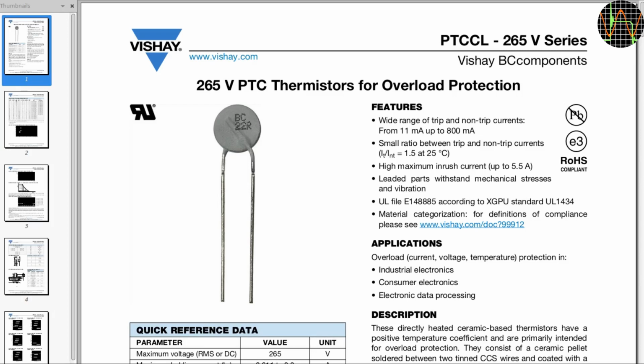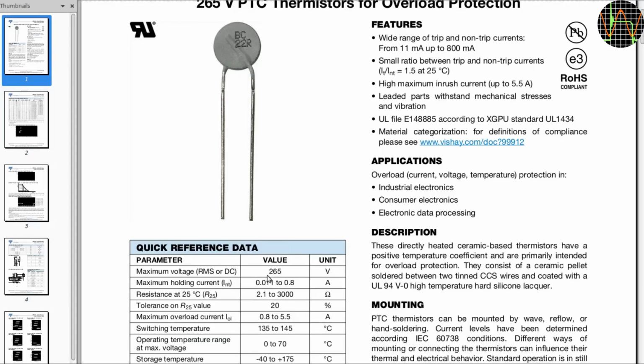I picked my thermistor from this datasheet from Vishay for the simple reason that almost all through-hole PTCs RS Components offers are from this series. However, I'm sure the same principle applies to other brands. As a start, we want to make sure that this PTC is suitable for mains voltage application, which is true for this series, which is rated for up to 265 volts RMS or DC voltage. There are thermistors for automotive use which are not suitable for this modification.